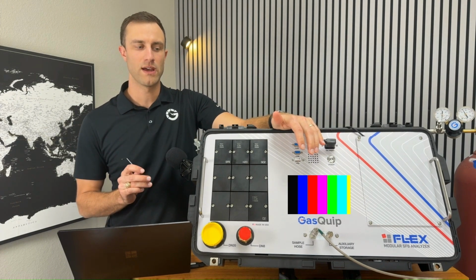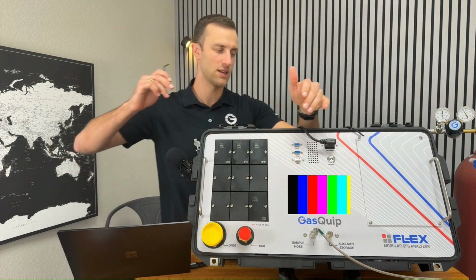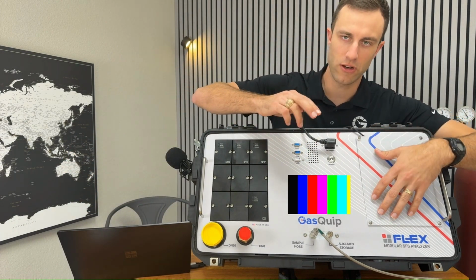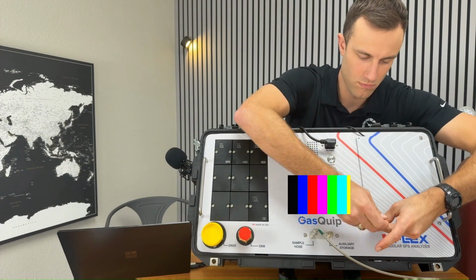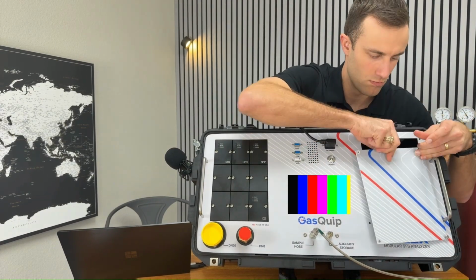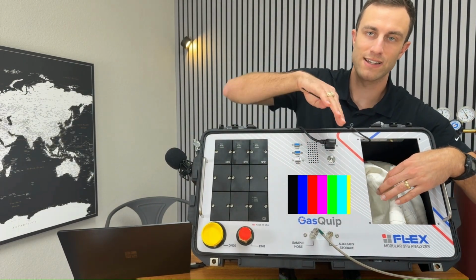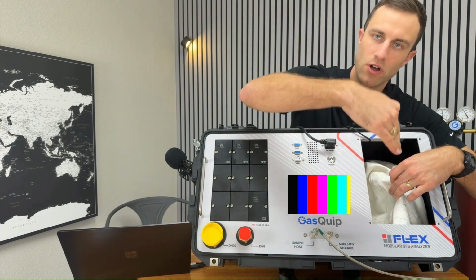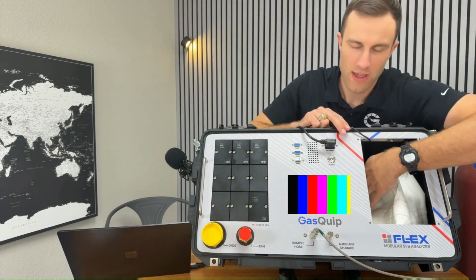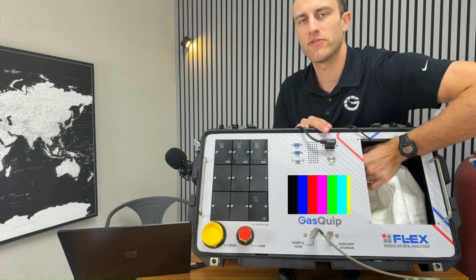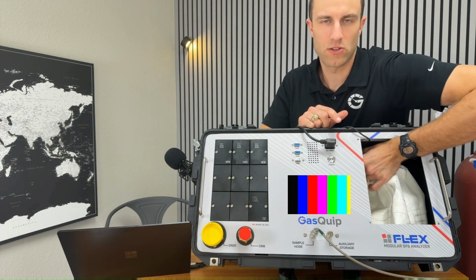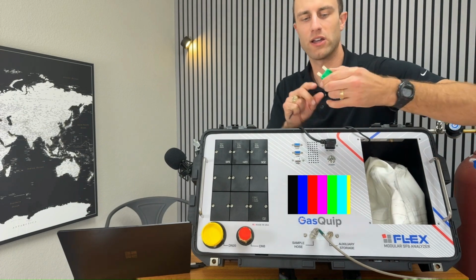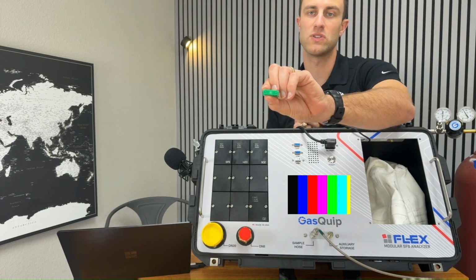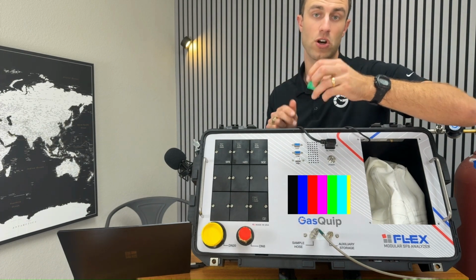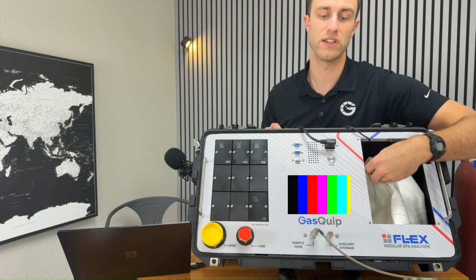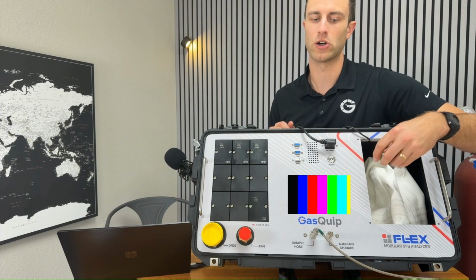If you have no luck with those troubleshooting steps, take off the panel here like I'll do now. There is an access panel that sits vertical on this side near the bag, and there is a small fuse that sits back here. It's a little green fuse. You can pull that out and check to make sure that that 30 amp fuse is intact and installed correctly. If it is, you want to go ahead and reinstall it and then try to power the unit back on.